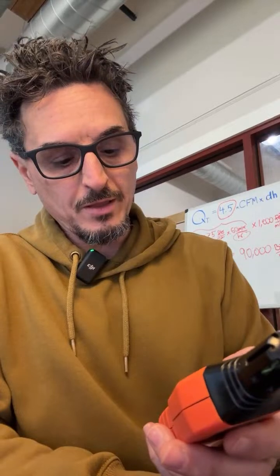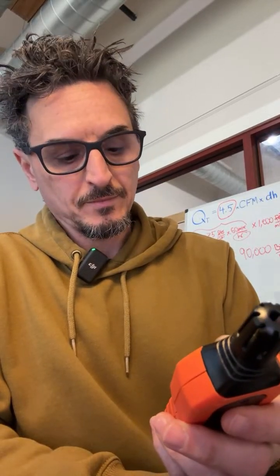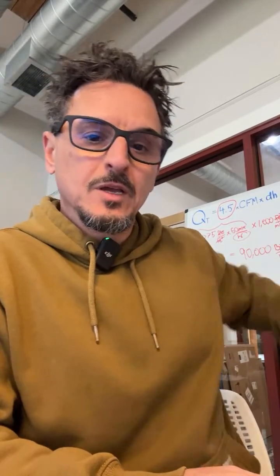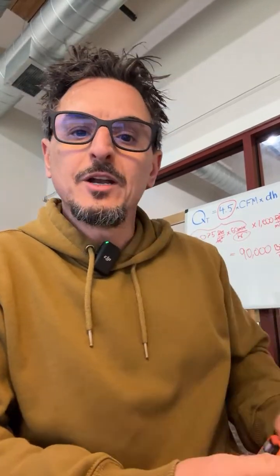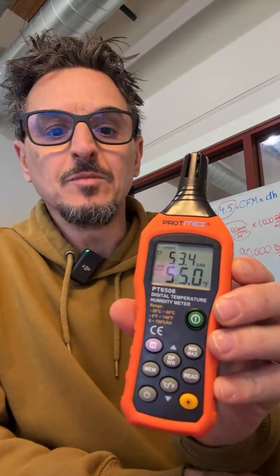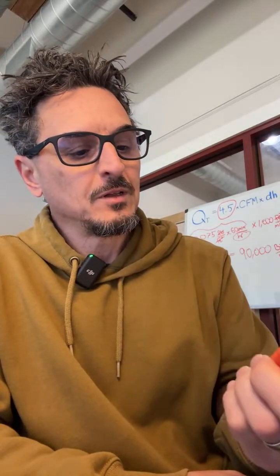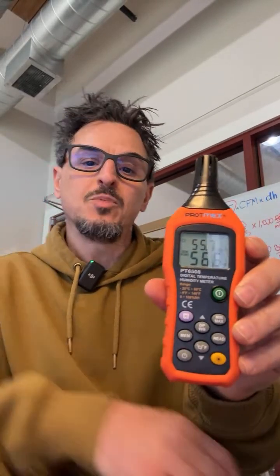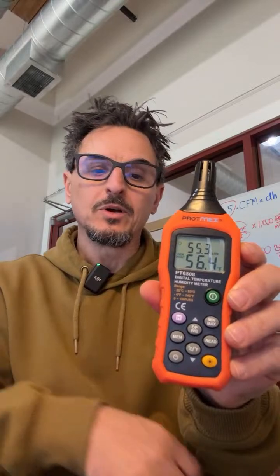Okay, so the dew point in this office, I'm going to shake this because it got the humidity on it from our last example. The dew point is about 55 degrees dew point. So what does that mean? That means any surface temperature that's colder than dew point of 55, 56, 57, it's going up probably because it's reading my breath, is going to condense water. So the dew point is an indicator of when water will condense on the surface.